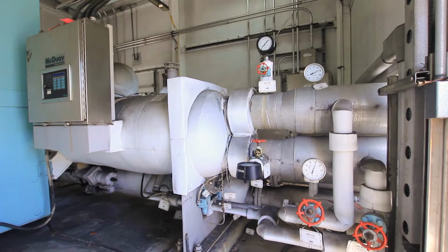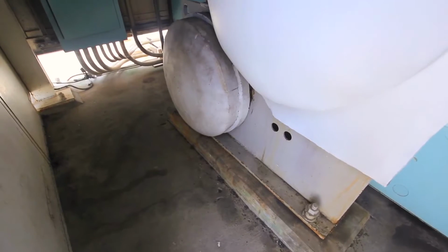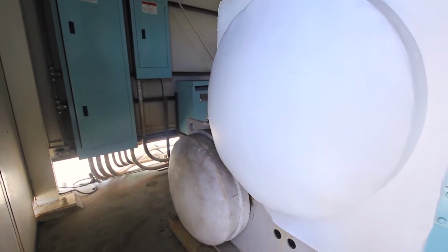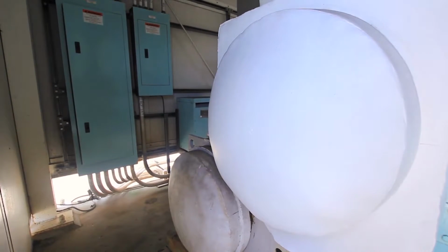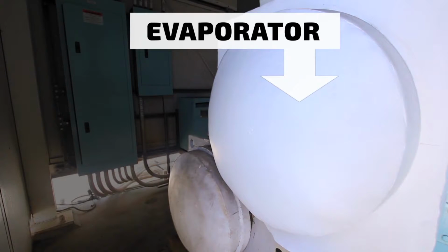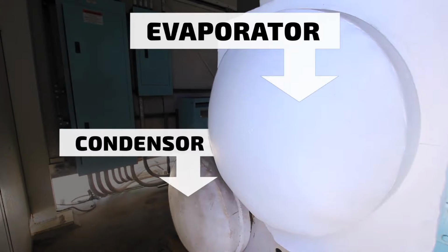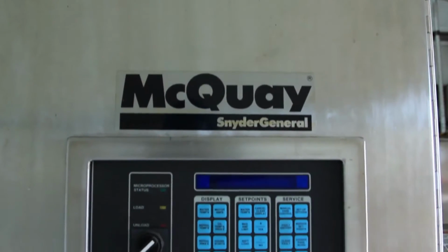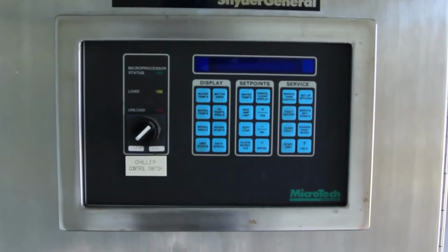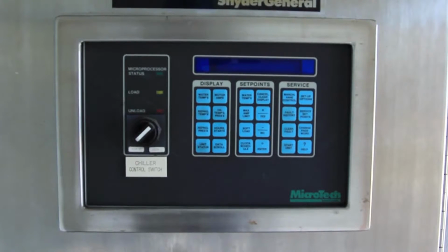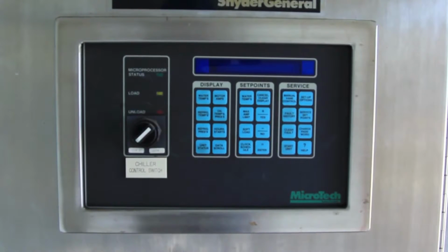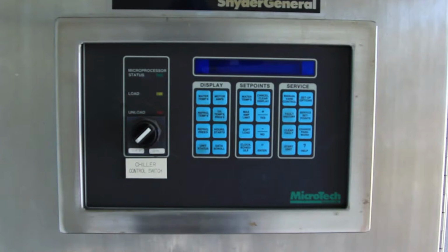A couple of other things you'll notice on the positive pressure machine. There's two separate vessels instead of a common vessel as on the low pressure appliance. On this machine, the evaporator is on top and the condenser is on bottom. This machine uses a digital microprocessor control device. The operator can select what parameters he needs to look at instead of looking at individual gauges throughout the machine.